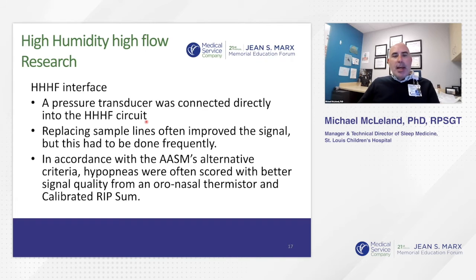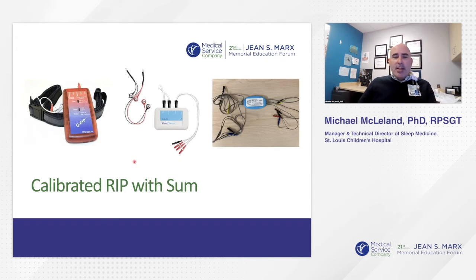According to the AASM's alternative criteria to score respiratory events, we could use the thermistor or the calibrated RIP sum. The calibrated RIP sum is basically the chest and abdomen effort being introduced into a module. That device then creates an algorithm that generates a flow, using a mathematical equation to create the flow. And basically what it comes out to, we have...